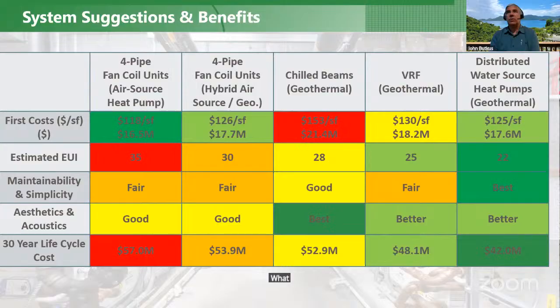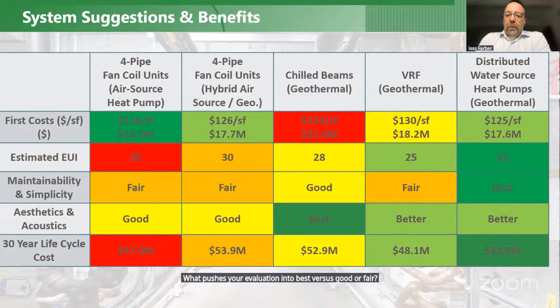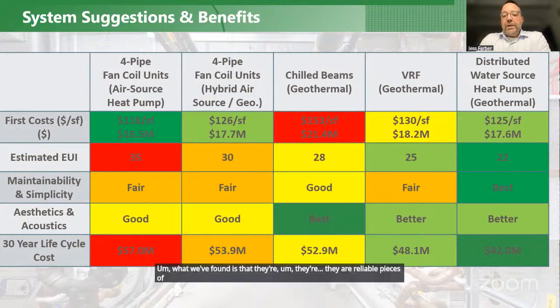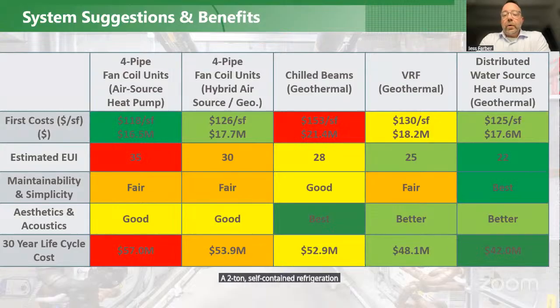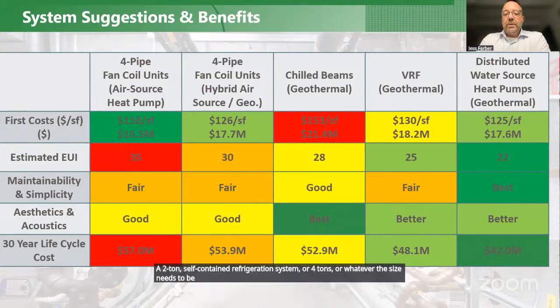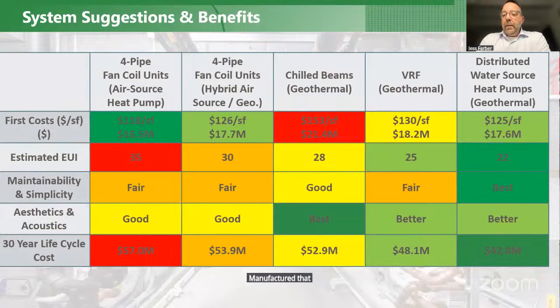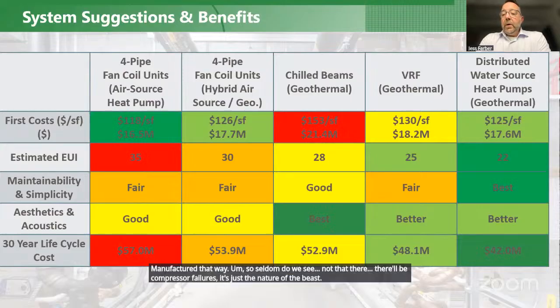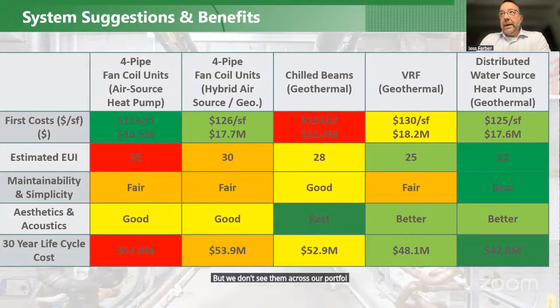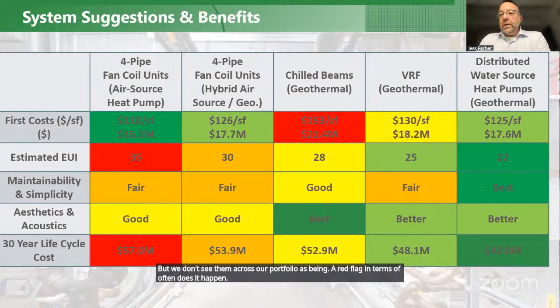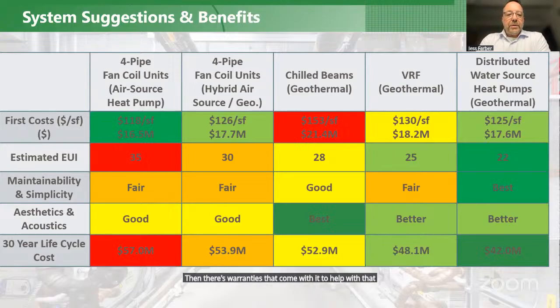What pushes your evaluation into best versus good or fair? What we've found is that they are reliable pieces of equipment. Each of those heat pumps is a 2-ton self-contained refrigeration system, or 4 tons, or whatever size it needs to be to take care of those classrooms. It's manufactured that way, so seldom do we see compressor failures -- it's just the nature of the beast, but we don't see them across our portfolio as being a red flag in terms of how often it happens. And there are warranties that come with it to help with that for a period of time as well.